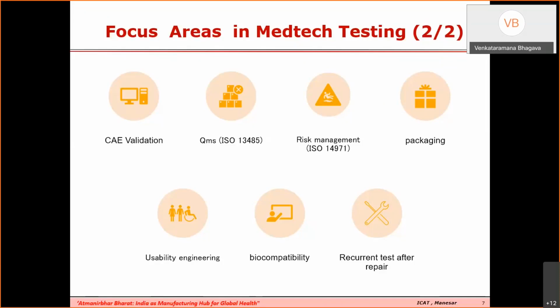Since some of you will be anesthesiologists, and sir is an anesthesiologist, I will point out one thing which I noticed while testing ventilators or respiratory care devices. In ventilators, you have PEEP, positive end expiratory pressure. I have observed that during these immunity tests, the PEEP starts to oscillate, and that could be quite harmful for the patient, I guess. Once, we were doing a test known as power frequency magnetic field, PFMF, and oscillations of power frequency were showing in the PEEP also. I think that will be harmful for the patient.